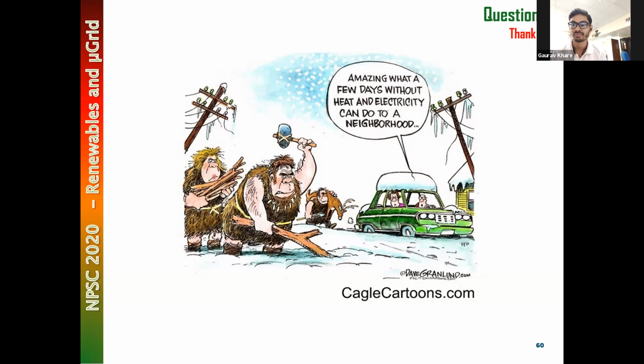The examples which I presented to you are realistic microgrids. Obviously, if your microgrid is very meshed, then you will need more than two setting groups. How do you change the setting groups, depending on sources? It could become what you call adaptive protection. Either you use setting groups or you use adaptive protection. It will depend on the topology of a microgrid how many setting groups you need.